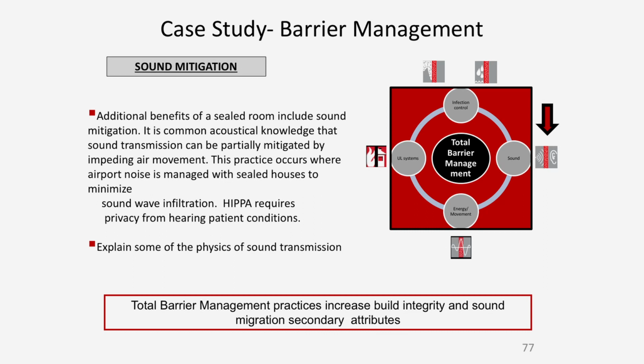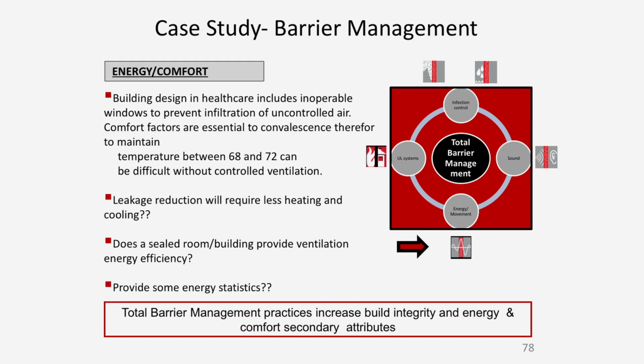In addition, because the rooms are sealed, there's less need for heating and cooling since the air doesn't escape. One untold consequence we had, especially on our bone marrow ward, which was 26 beds, was that we couldn't close the suite doors - the doors to the unit would not close. Why? Because the air was not leaking away. When they design a hospital or most buildings with mechanical systems, they design in a leakage rate. If you eliminate that leakage rate, where's the air going to go? It was trying to go out the front door and couldn't close it.